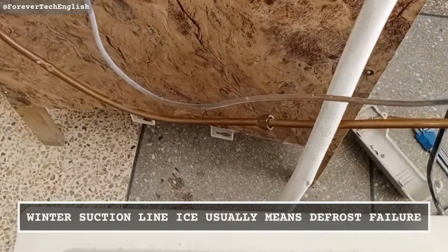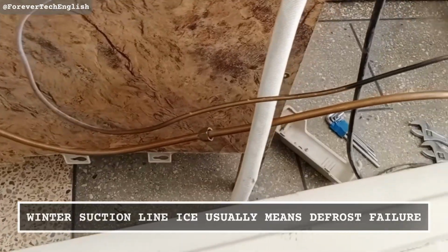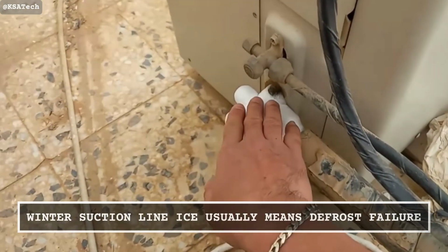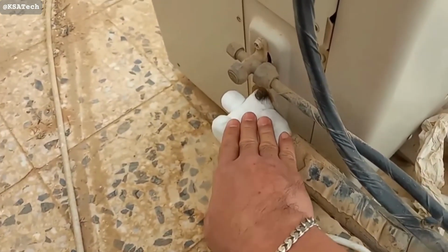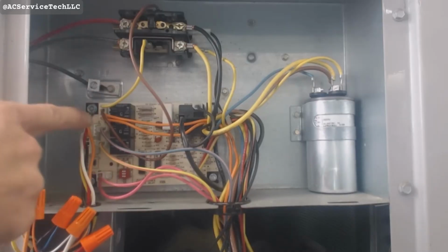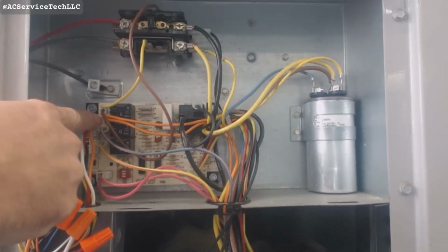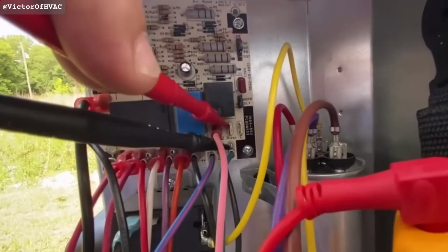Number 19. Suction line ice on a heat pump in winter is not a refrigerant problem. It's a defrost cycle problem. The defrost board is either failing to initiate the cycle on time or the defrost thermostat sensor has lost contact with the coil. Don't let a contractor sell you a recharge for a control board issue. The recharge will mask the symptom for one cycle, then come right back.